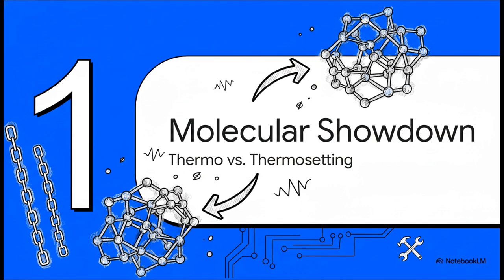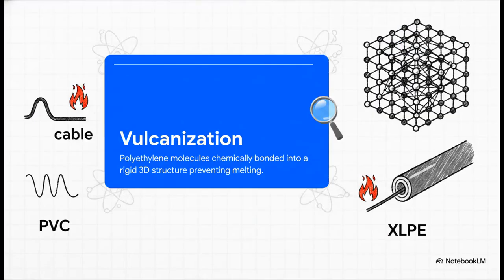Thermoplastic versus thermosetting. This is where we look at the fundamental chemical differences that literally dictate how these materials perform. What's really interesting about this slide is the concept of vulcanization. PVC, or polyvinyl chloride, is a thermoplastic material. Simply put, that means it softens and can actually deform when it gets heated up. But XLPE undergoes this vulcanization process. The polyethylene molecules are chemically bonded, or cross-linked, into a really rigid 3D structure. That essentially turns XLPE into a thermosetting plastic. Once it's set, it is set. It simply will not melt at high temperatures the way PVC does.